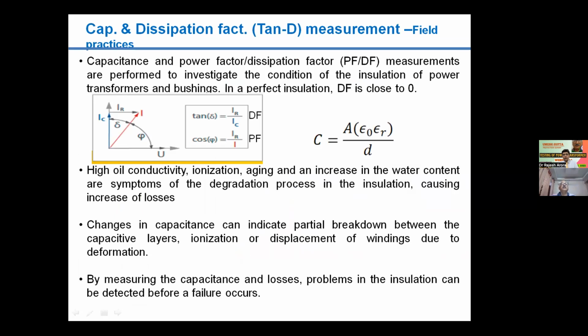Next is the capacitance and dissipation factor, tan delta, measurement. As you know, another vital test on the power transformer in the field is the testing of its insulation: the solid insulation in the form of impregnated paper, and the insulating oil. In addition to oil and paper, there are other components like press boards, and other structures are also there.